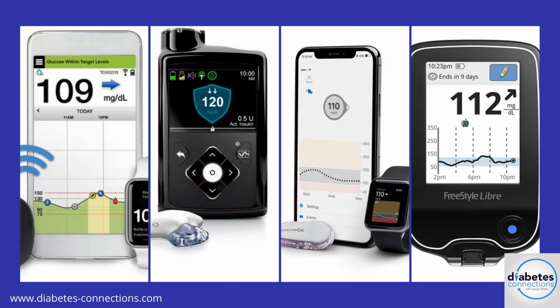Another issue we often see is that if the transmitter and sensor bend against each other, the transmitter may start to lose connection periodically. So place it so that the sensor and transmitter are on a relatively flat, linear surface. I know in the human body there's not a lot of flat linear surfaces, but for example, if it's on your arm, put it lengthwise, not sideways. Or if it's on your abdomen, put it on a flat area, not a curved area, if at all possible.